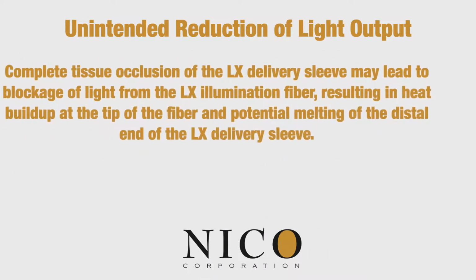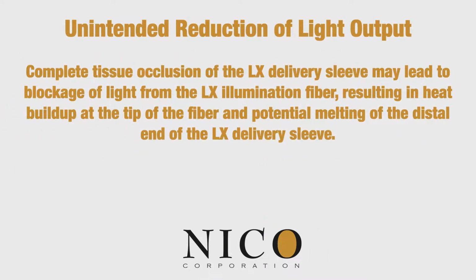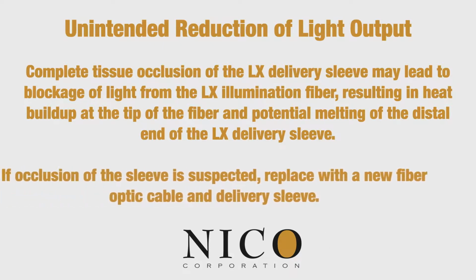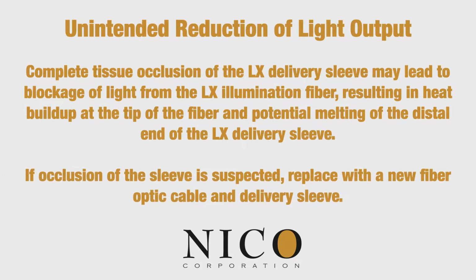Complete tissue occlusion of the LX delivery sleeve may lead to blockage of light from the LX illumination fiber, resulting in heat buildup at the tip of the fiber and potential melting of the distal end of the LX delivery sleeve. If occlusion of the sleeve is suspected, replace with a new fiber optic cable and delivery sleeve.